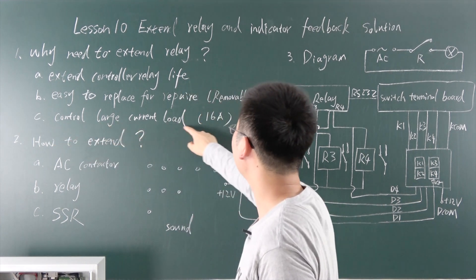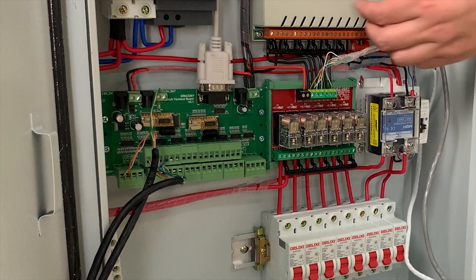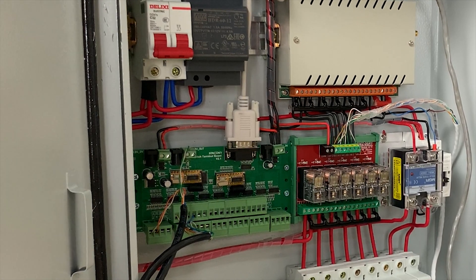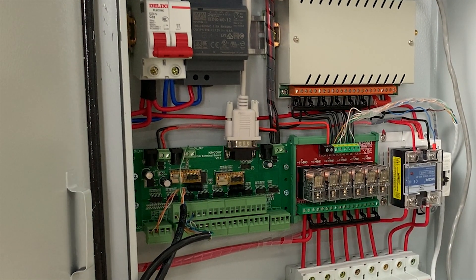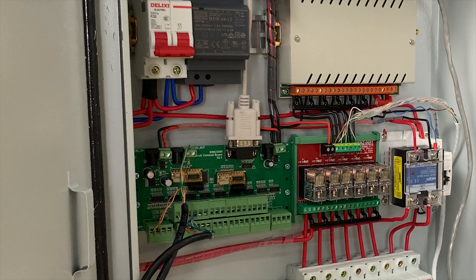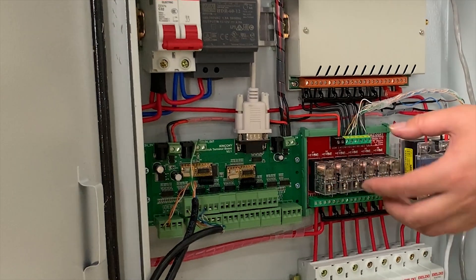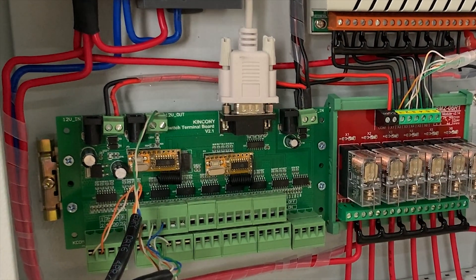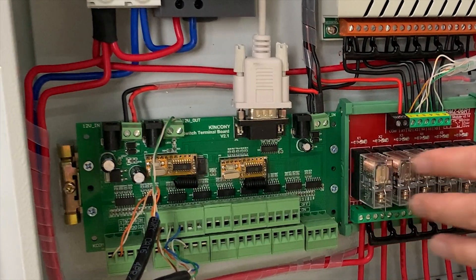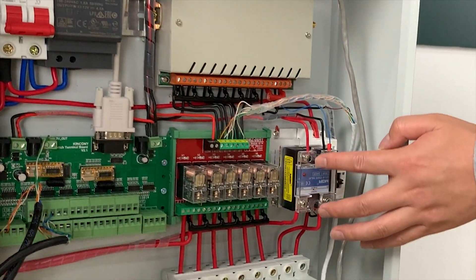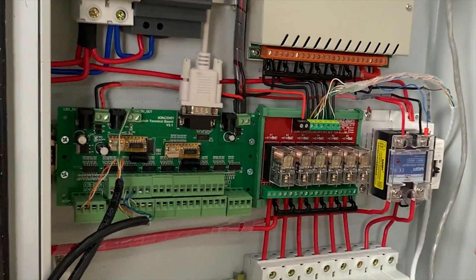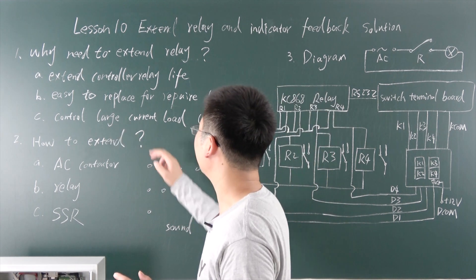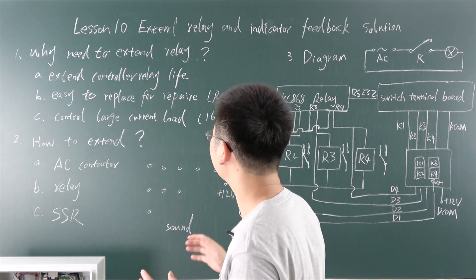The third reason is to control large current loads. The relay inside our box is rated at 10 amperes. If you need 16 amperes for air conditioning, or more — like 20 or 25 amperes — you just choose the appropriate external relay with the right current rating. I have installed eight channels here: a small-current relay, an SSR at 20 amperes, and an AC contactor at 25 amperes.